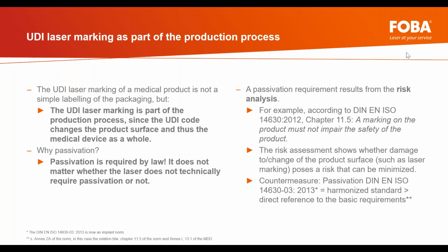So what's next here? Next here is to see that the passivation requirements are not just jumping out of my head and what I see in the market. So this is a result from risk analysis. For example, if we have the implant ISO 14630, the 2012 version, in chapter 11.5, it's saying a marking on the product must not impair the safety of the product. So that concludes that a risk assessment shows whether damage to or change of the product surface poses a risk that can be minimized.